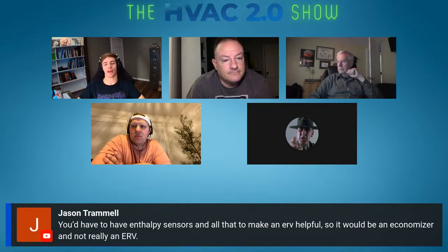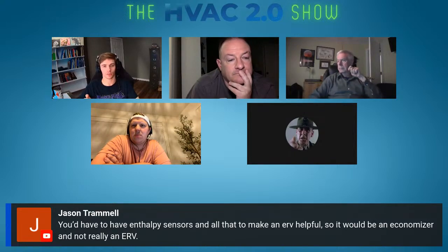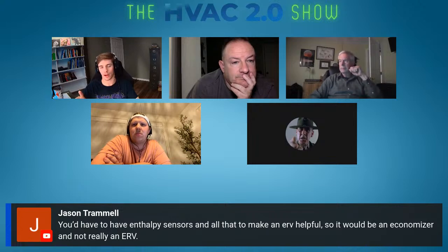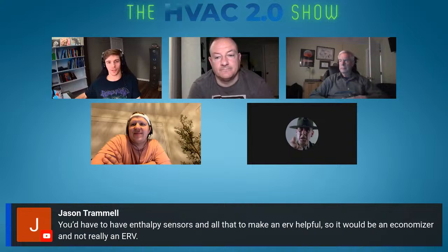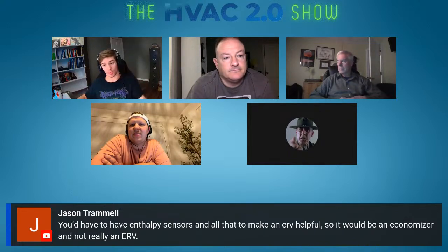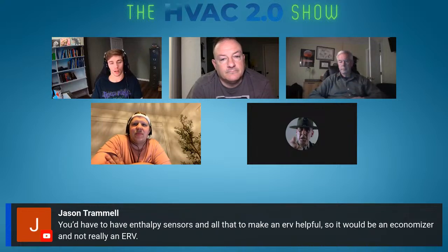And if I remember correctly, I think I saw a video of Matt's setup, and he was also using the Carrier mini split outdoor unit and air handler combo, the Midea brand. So he was already using something that was poorly set up for dehumidification, which qualifies why he needs the multiple dehumidifiers. And then he throws an ERV on top of it. So it's just this concoction of a lot of potential problems, a bunch of dumb stuff.